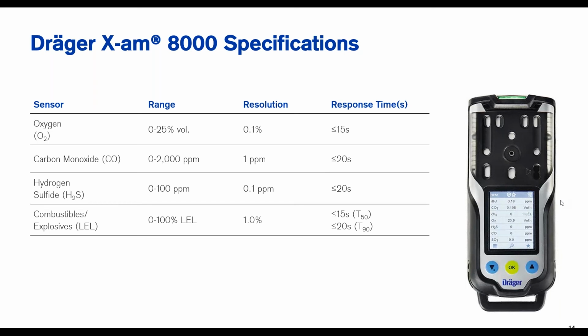Typical response time on that is around 20 seconds, less than or equal to 20 seconds. H2S, pretty much the same response time on that one. And then your combustibles, explosives, your LEL sensor, again, that's reading 0 to 100% of the LEL. And then they also have in this particular meter a T50 response time of less than or equal to 15 seconds, and then less than or equal to 20 seconds for the T90.